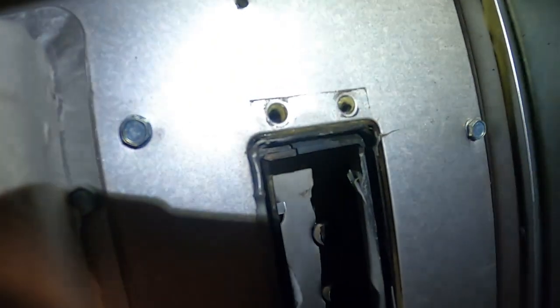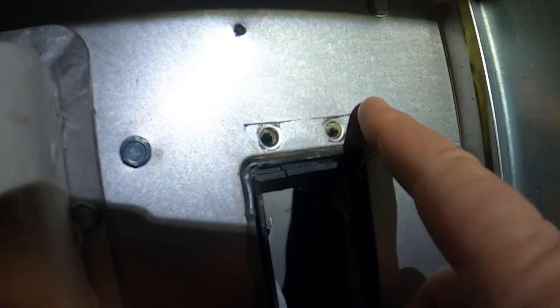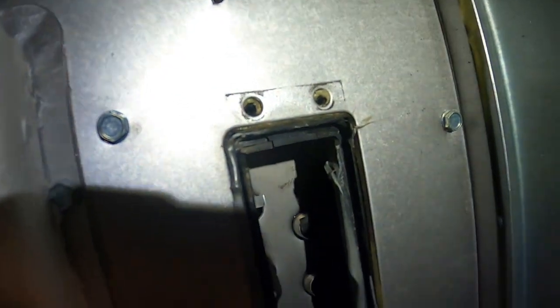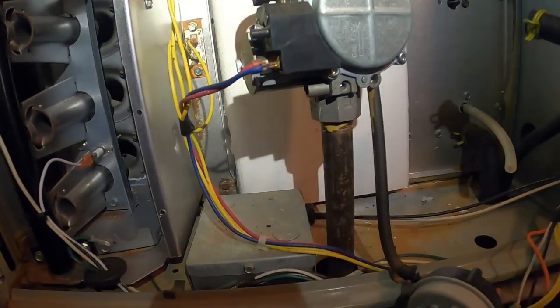And now you're screwed. Now you've got exhaust, and then you've got leakage, and the water sweats in there and runs down it. It's acidic because it's the flue exhaust, and then you get your rust.